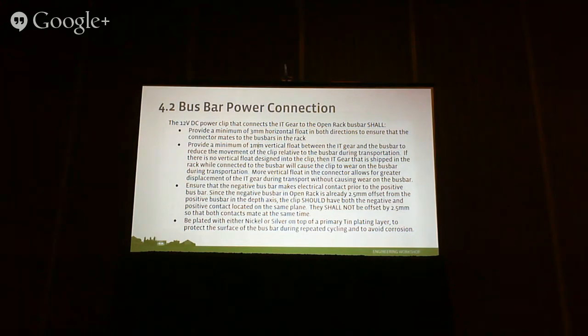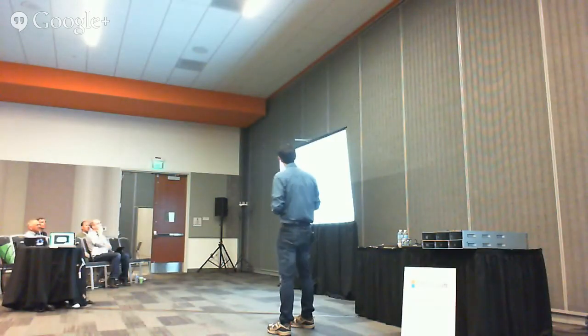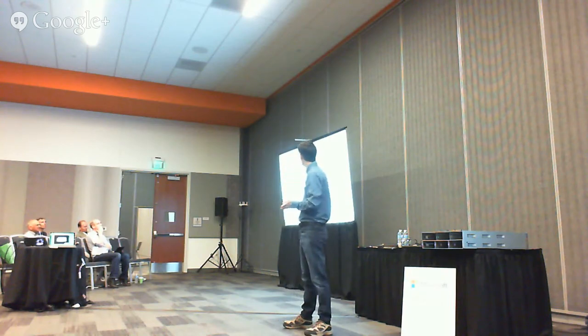So one key clip: any 12-volt power clip that connects IT gear to the Open Rack bus bar shall provide a minimum of 3 mm horizontal float direction. So this basically ensures that you can hot plug the bus bar without damaging either the bus bar or the clip itself. You provide a minimum of 1 mm vertical float in the bus bar to reduce the movement of the clip relative to the bus bar.